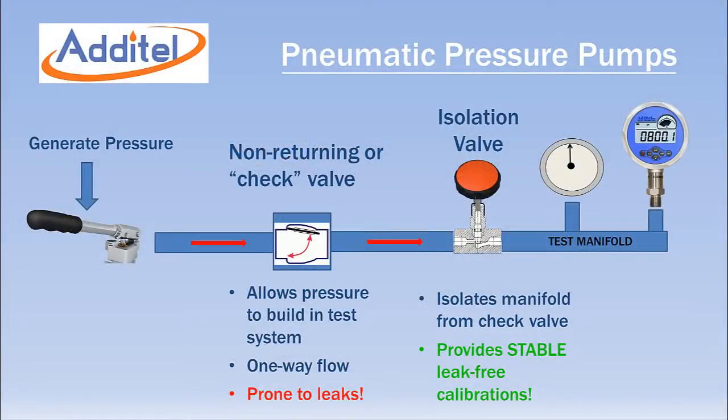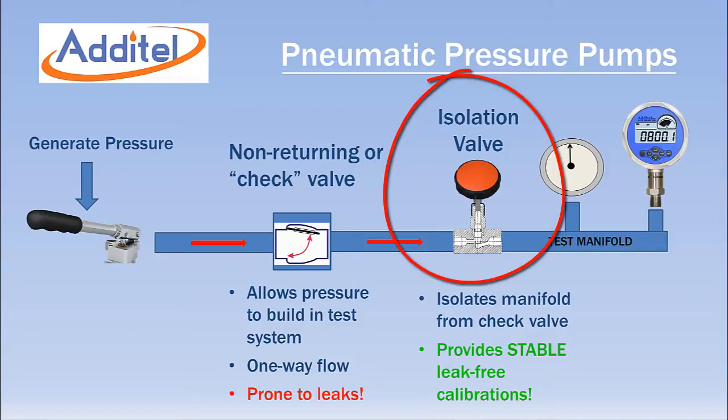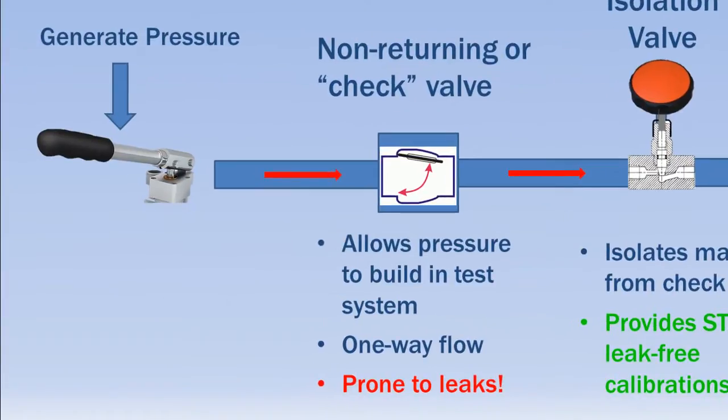A major design advantage of all Additel pneumatic pumps is an isolation valve that allows leak-free, stable calibrations. Most pneumatic pumps on the market have non-returning or check valves that allow pressure to be built up in the test volume. These valves are often prone to leakage as seals wear.